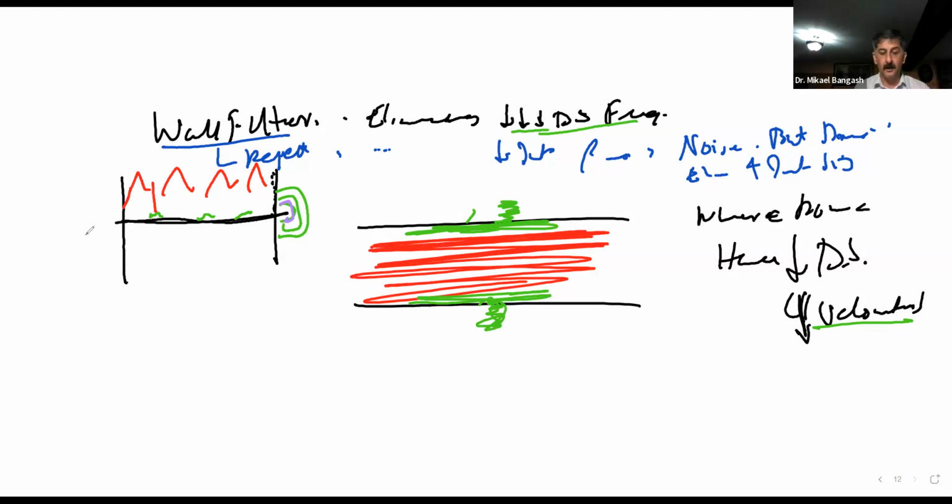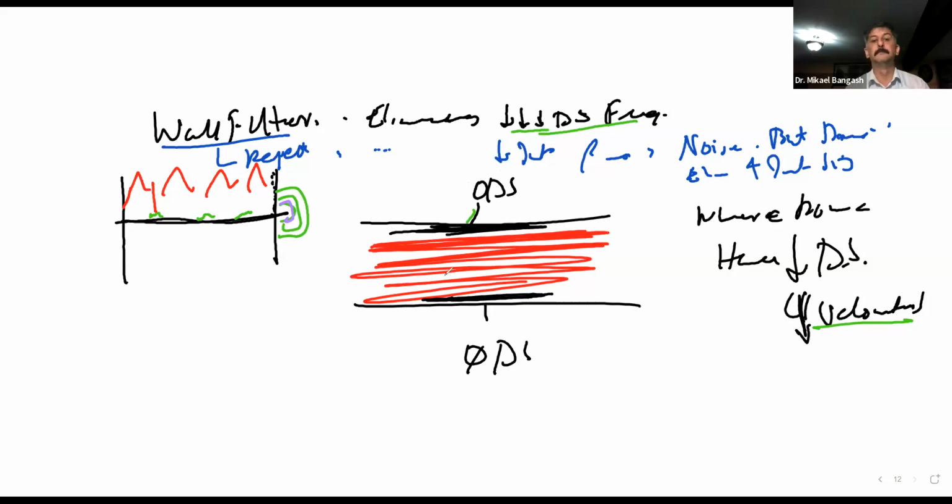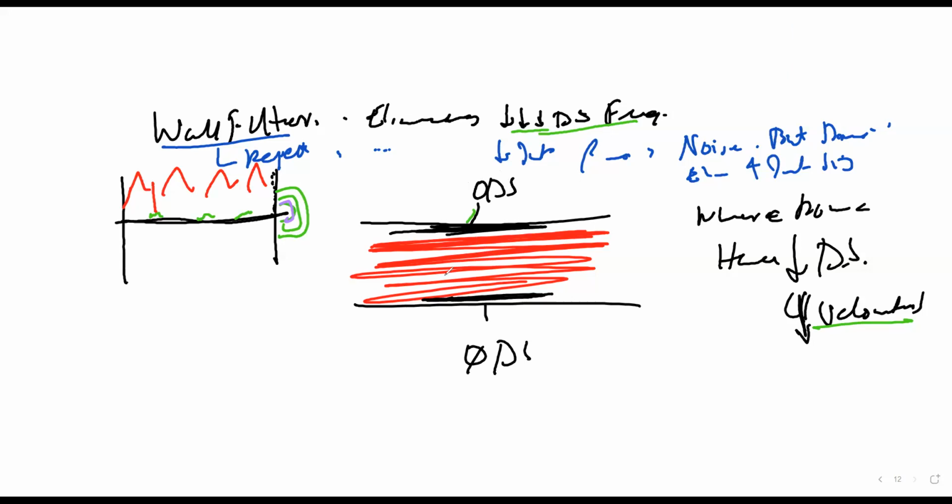So what may happen as you apply a filter here is that it may get rid of this and this, but if you keep on increasing it, it may also cause decreased filling of the blood vessel, where the periphery of the blood vessel may show zero Doppler shifts while the blood vessel becomes less and less filled. Is that clear? Yes. Right.